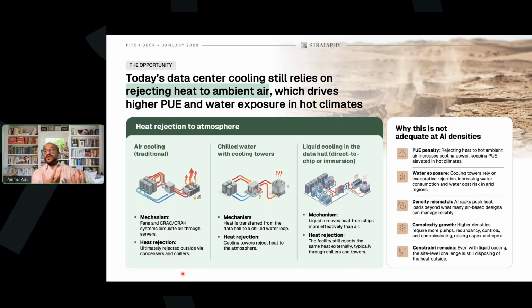So think about the cooling system. What does your HVAC typically include? It includes a compressor, and that compressor's refrigerant, which is 70, 80, or 60 degrees Celsius depending on where you are, goes to a condenser unit. This condenser unit only has heat rejection. It has fans that blow onto this compressed refrigerant. That heat dissipates because the compressed refrigerant is actually warmer than the temperature outside. So you're technically rejecting heat into the ambient condition.